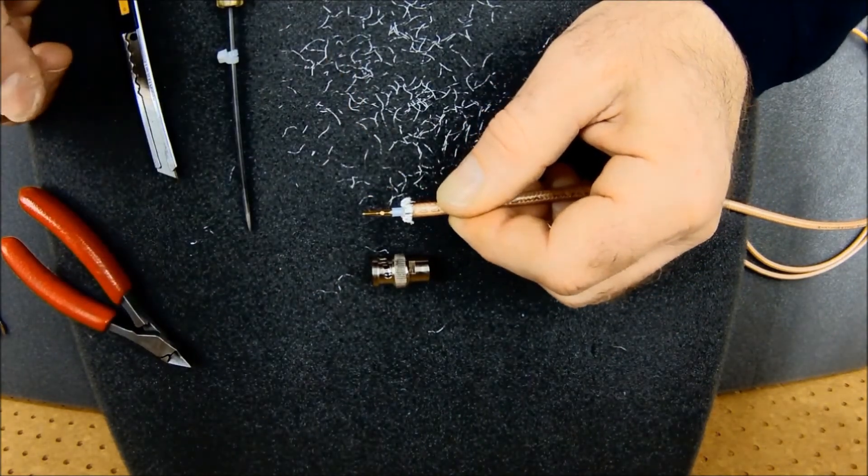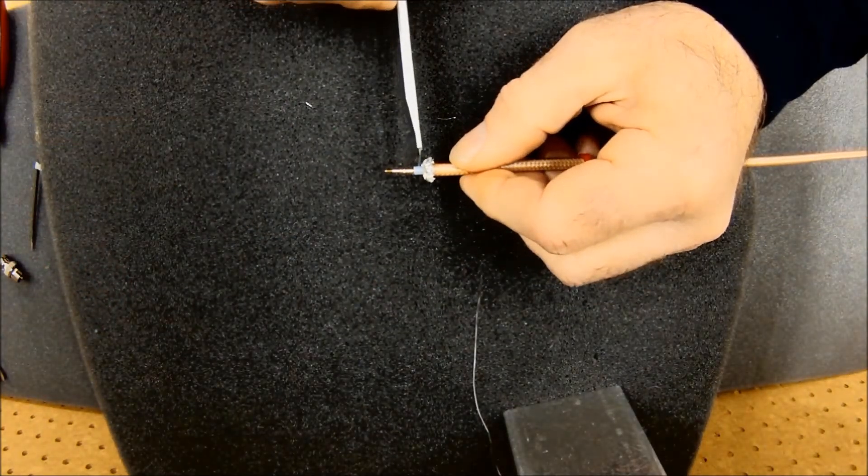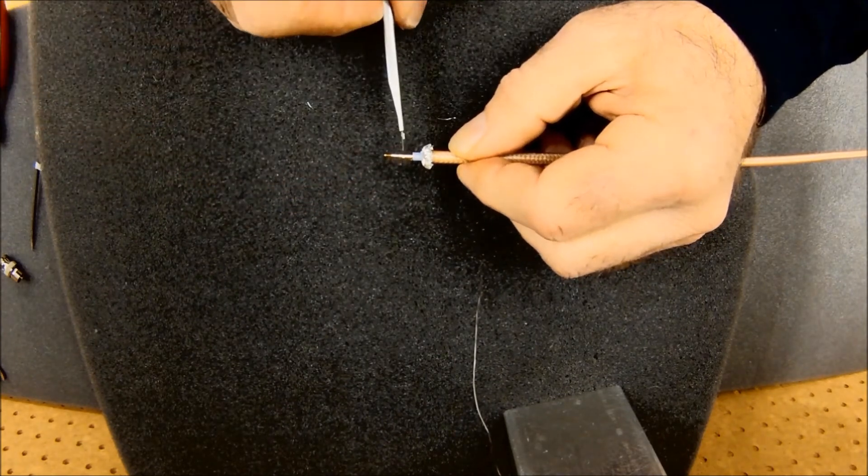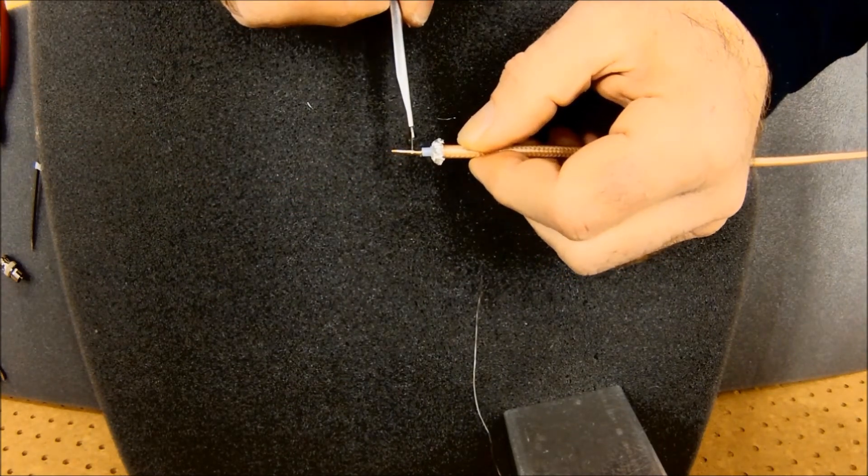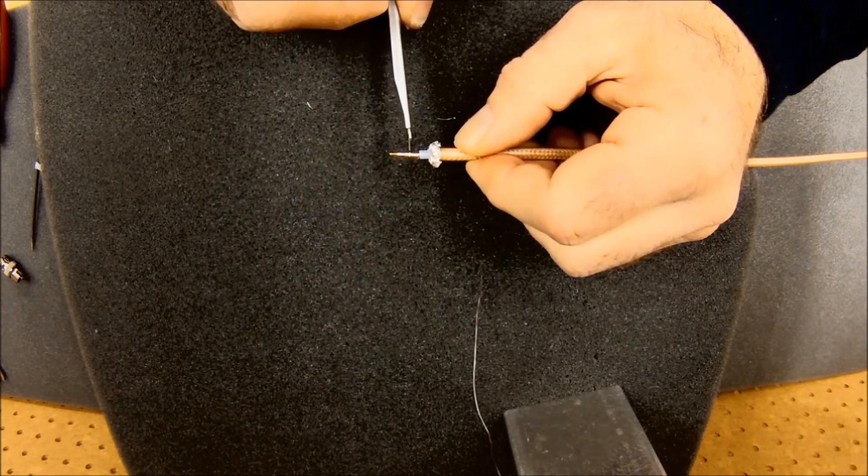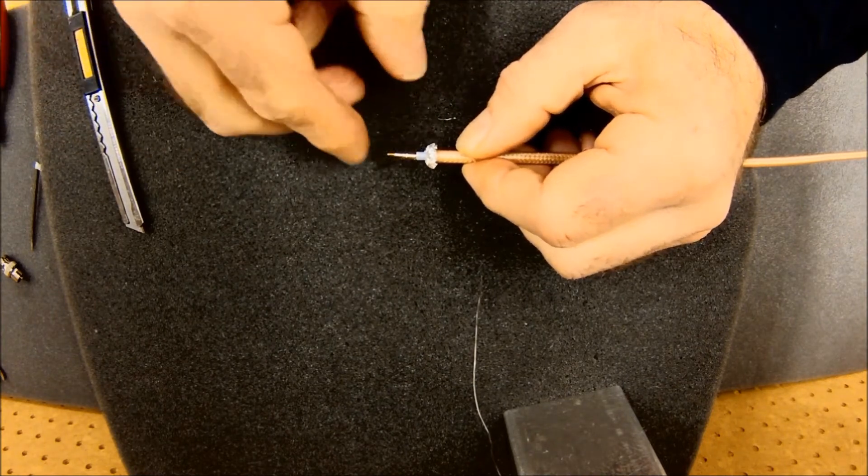And I can put this center conductor on. Notice this seats right up against the dielectric. And I can see, it might be hard to see on the video here, but I can see in that little inspection hole. I can see the center conductor wire. So I know I'm in the right distance.